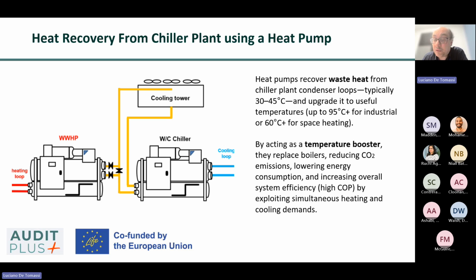A heat pump can be integrated into this system to recover heat and lift that heat to a higher temperature suitable for end-use applications. The heat pump effectively acts as a temperature booster. It takes the relatively low temperature condenser return water as its source, and using electrical energy to drive a compressor cycle, increases the temperature of the recovered heat to a usable level. Depending on the design and refrigerant selection, this upgraded heat can reach around 60 degrees Celsius or higher for space heating applications, and in high temperature industrial heat pump systems, it can exceed 90 degrees Celsius for process heating or hot water systems.